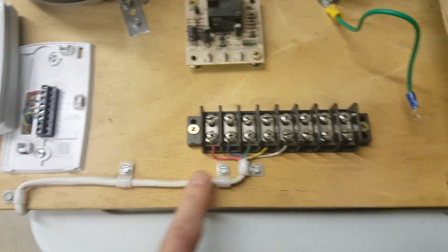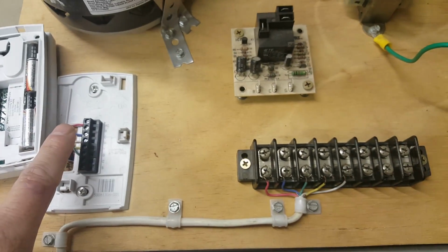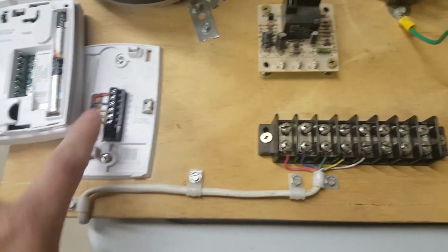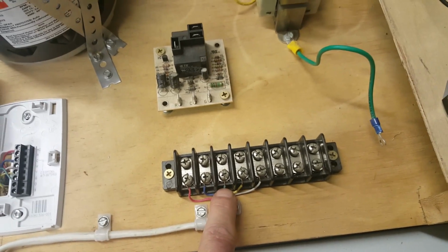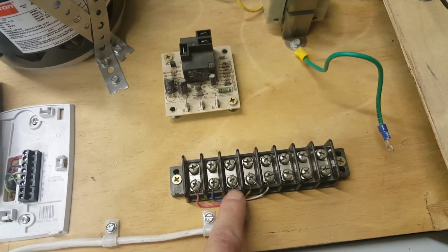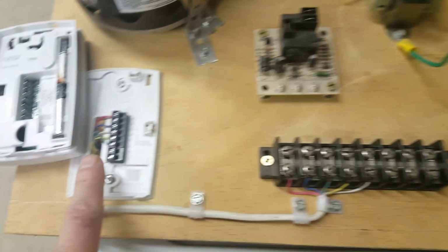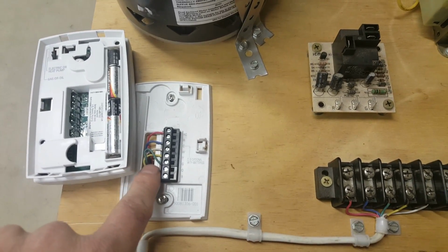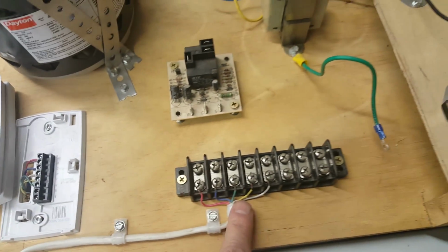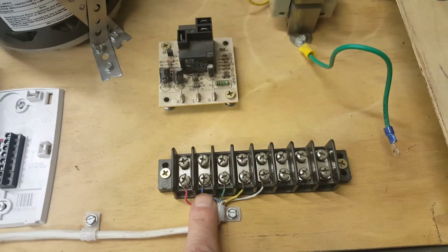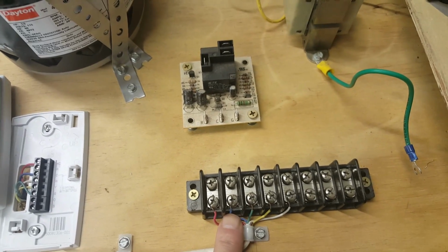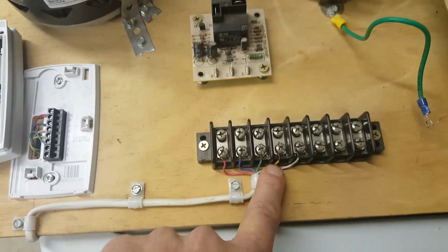The 24 volt hot goes out to the thermostat, and that's as far as it goes. When the thermostat calls for fan, it will take a ride back on the G circuit, which completes the power wire back to here to go to the fan relay. If we're calling for cooling, then we're going to have power. The R wire is going to take a ride on the Y cooling circuit and the G circuit. So we would actually have 24 volts from the 24 volt common here to the G circuit, or 24 volt common to the cooling circuit.